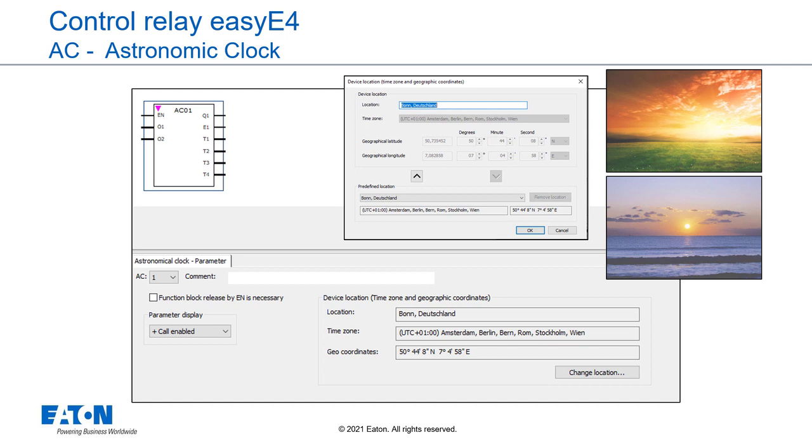The Astronomic clock function block is meant for use in latitudes of minus 65 to plus 65. Outside these latitudes, the calculation of the times for sunrise and sunset becomes too inaccurate. At a latitude of 60, the average inaccuracy is up to 5 minutes. At a latitude of 65.7, the inaccuracy is about 12 minutes.